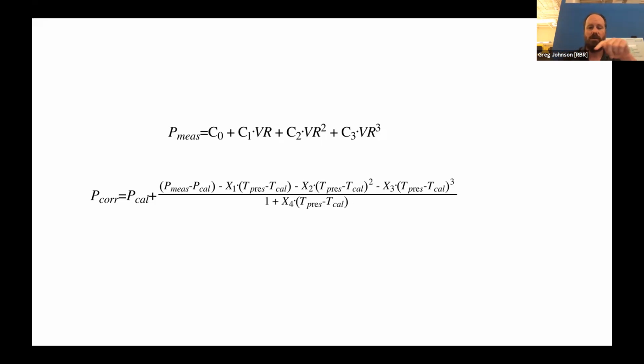And so you can see that we've got a cubic against the voltage ratio, but we've also got a cubic against the deviation of the temperature that the instrument is running at versus the temperature that we calibrated at in the first place. So that is what these cross calibration coefficients are, x1, 2, 3, and 4.